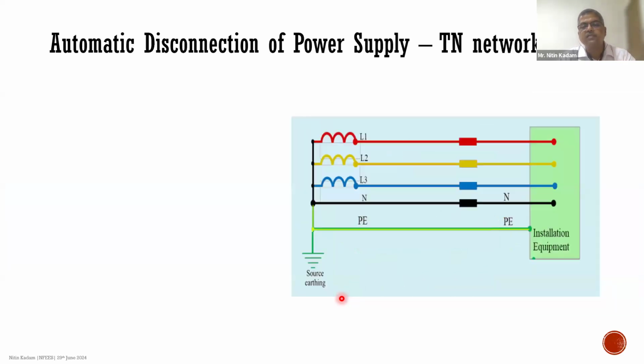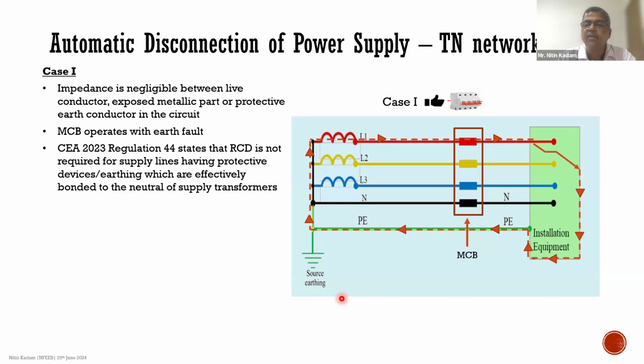Let us see how the automatic disconnection of the power supply will happen in case of TN network. Whenever there is a fault happening, if the fault loop impedance value is according to the values that are specified in the chart we have seen earlier, in that case, the MCB will trip. And this is a welcome condition. This is how it has to operate, so that the people who are working on the site, on the equipment, that is maybe either the technician, or if there are end users of the equipment, they are protected.